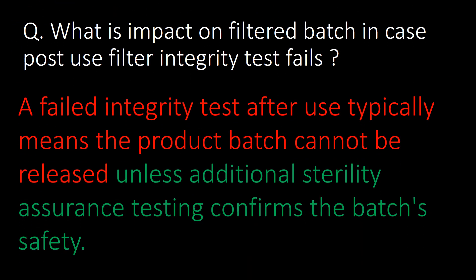What is the impact on the filtered batch in case a post-use filter integrity test fails? A failed integrity test after use typically means the product batch cannot be released unless additional sterility assurance testing confirms the batch's safety.